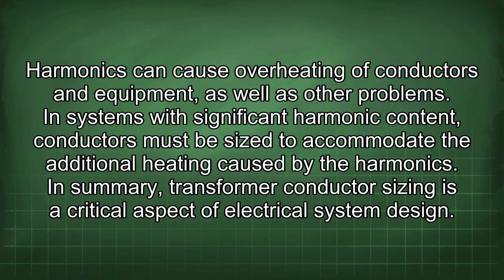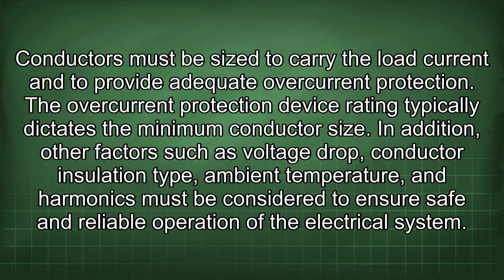In summary, transformer conductor sizing is a critical aspect of electrical system design. Conductors must be sized to carry the load current and to provide adequate overcurrent protection. The overcurrent protection device rating typically dictates the minimum conductor size. In addition, other factors such as voltage drop, conductor insulation type, ambient temperature, and harmonics must be considered to ensure safe and reliable operation of the electrical system.